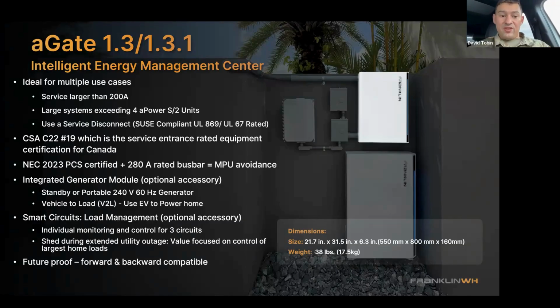We are NEC 2023 PCS certified with a 280 amp bus bar inside our gateway. We are also certified under CSA number 19 for service entrance rated. But depending on your AHJ, you may still need to get an Eaton disconnect, depending on what they think of that certification.